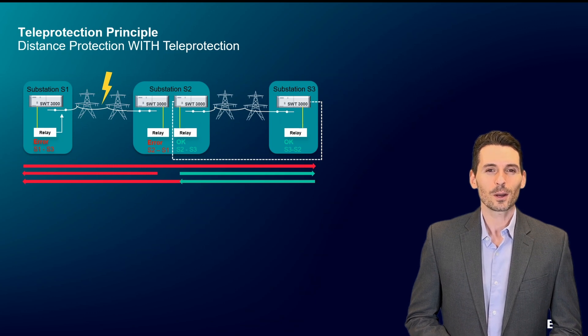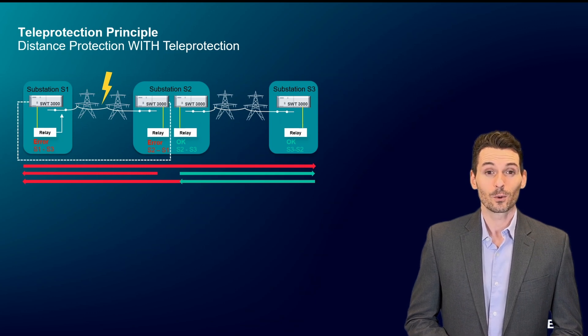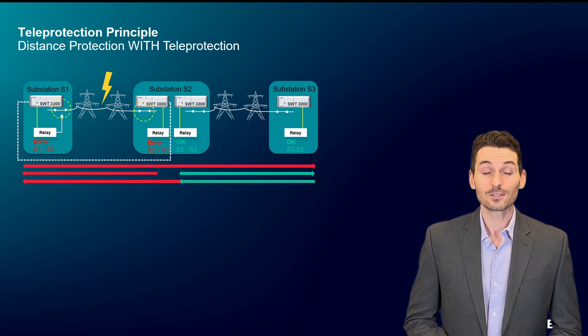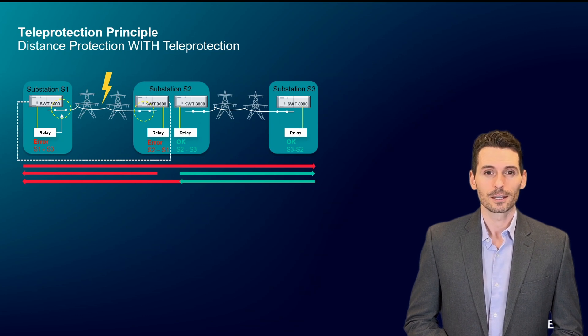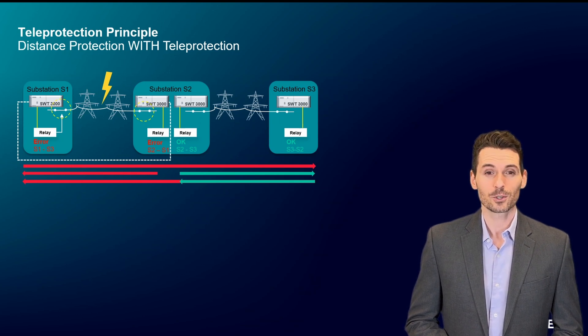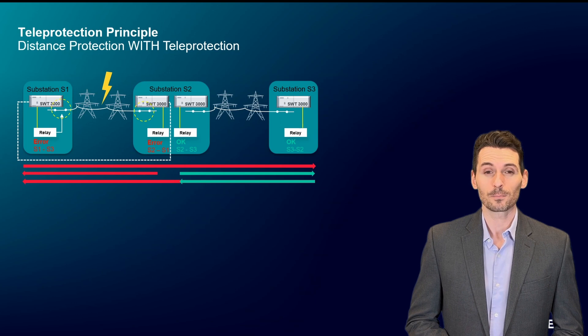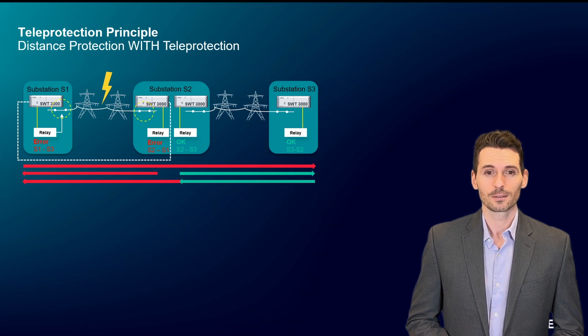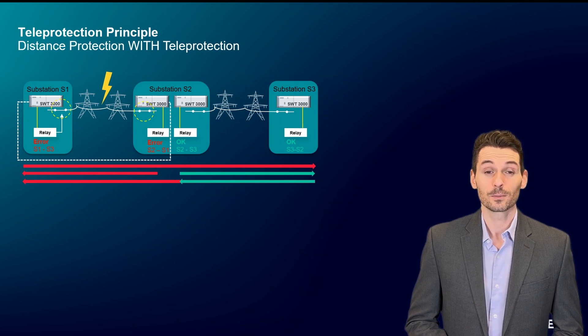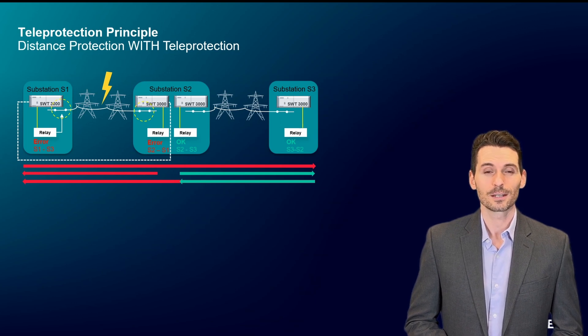Both relays report a network error between substations 1 and 2 to the protection signaling systems. This means both substations 1 and 2 detected an error between each other. The result is sent back to the protection relays.